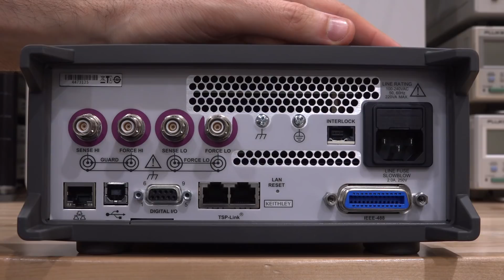First of all, there are 3 ways to connect this instrument to the PC: GPIB for legacy support, USB, and Ethernet. Ethernet is particularly useful if you want to have this reasonably far away from your computer or connected to a network. There's also the digital I/O, which can be used with internal triggering or external software in order to have some interaction with the device and trigger on some event, for instance.